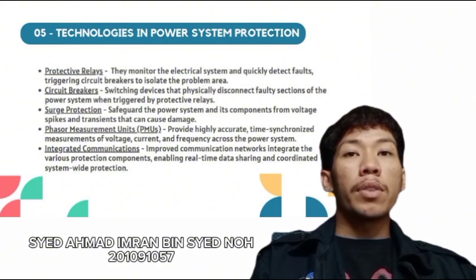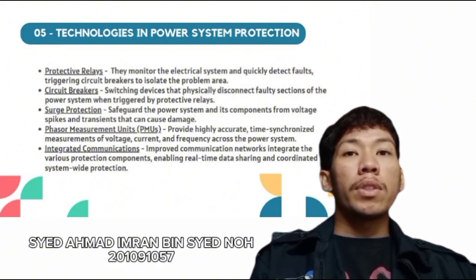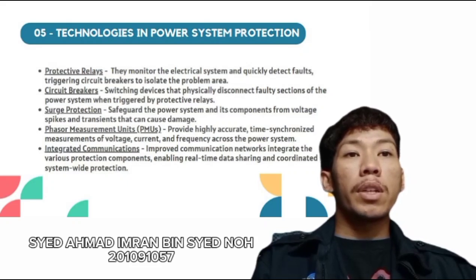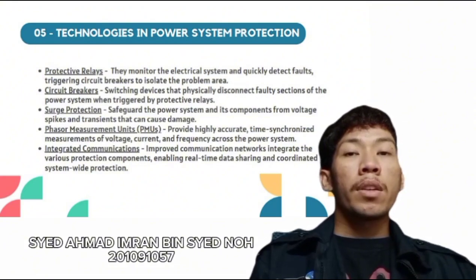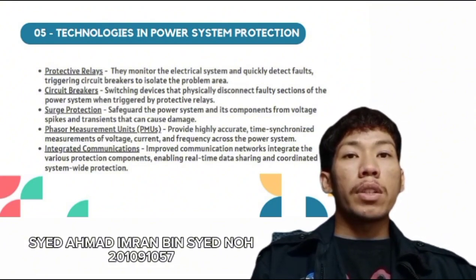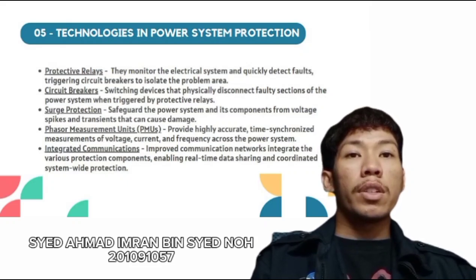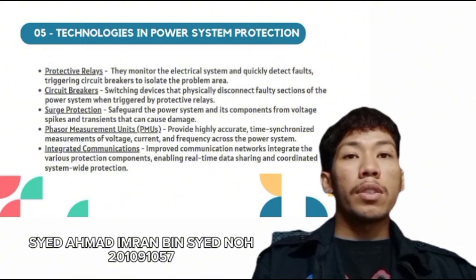So I'm going to talk about the technologies in power system protection. There are five. The first one is the protective relay. They monitor the electrical system and quickly detect faults, triggering the circuit breaker to isolate the problem area. The second one is the circuit breaker. It is a switching device that physically disconnects the faulty section of the power system when triggered by the protective relay. And the third one is surge protection. It safeguards the power system and its components from voltage spikes and transients that can cause damage.